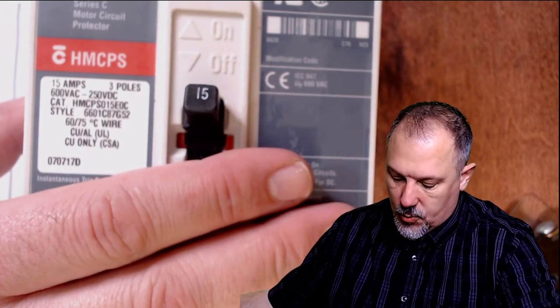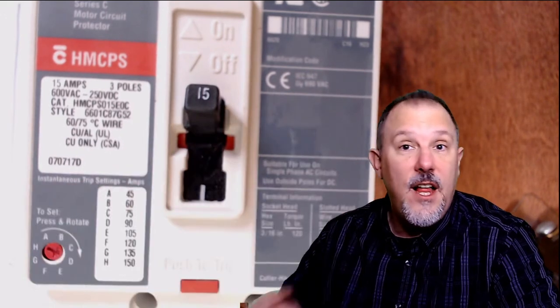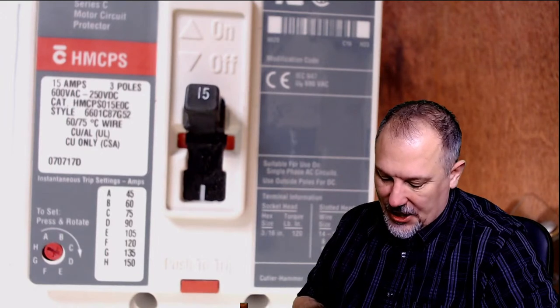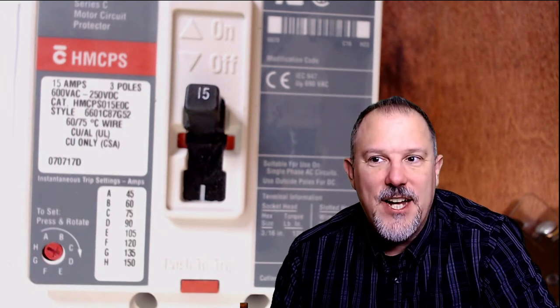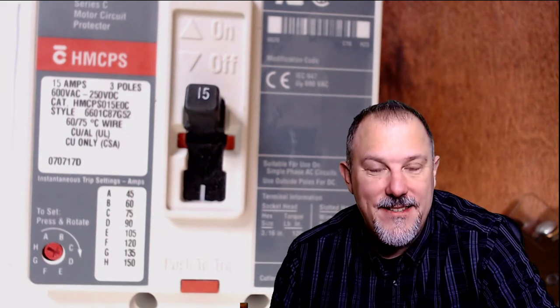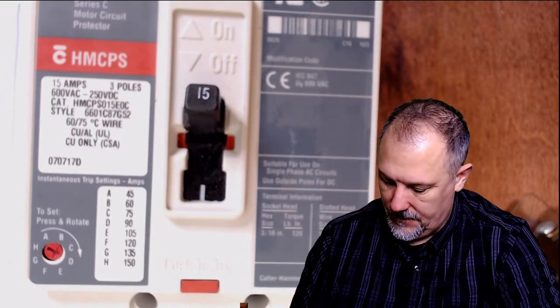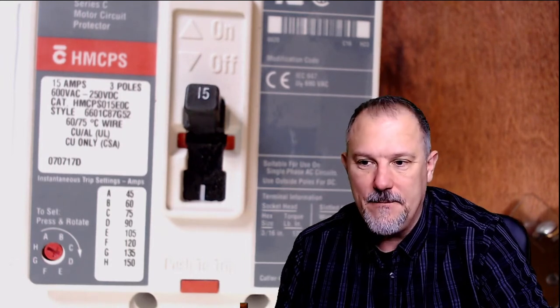Circuit breakers used as switches in 120 volt and 277 volt fluorescent lighting circuits shall be listed and shall be marked SWD or HID. Fluorescent. Did you know that? If you are switching fluorescents, remember, this is used as switches. When would you use that?